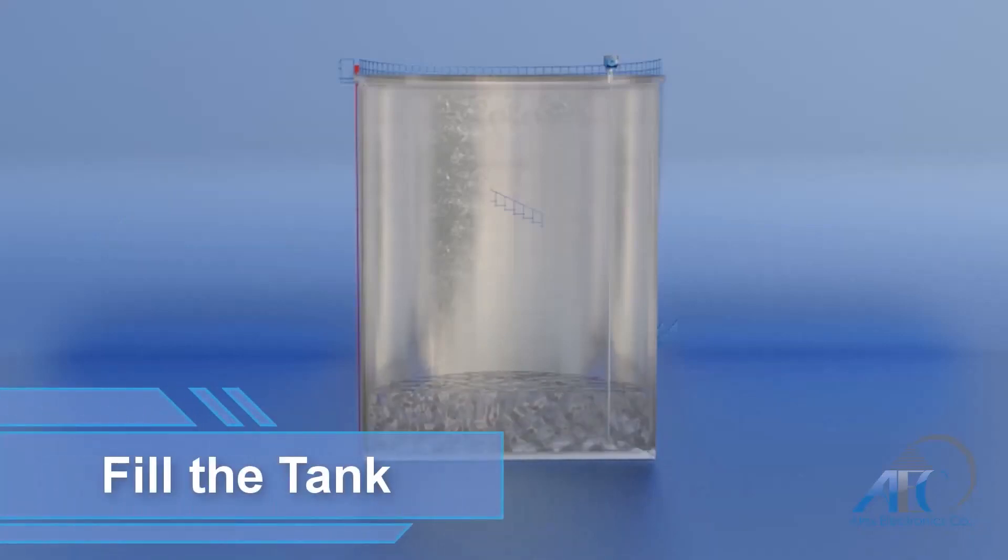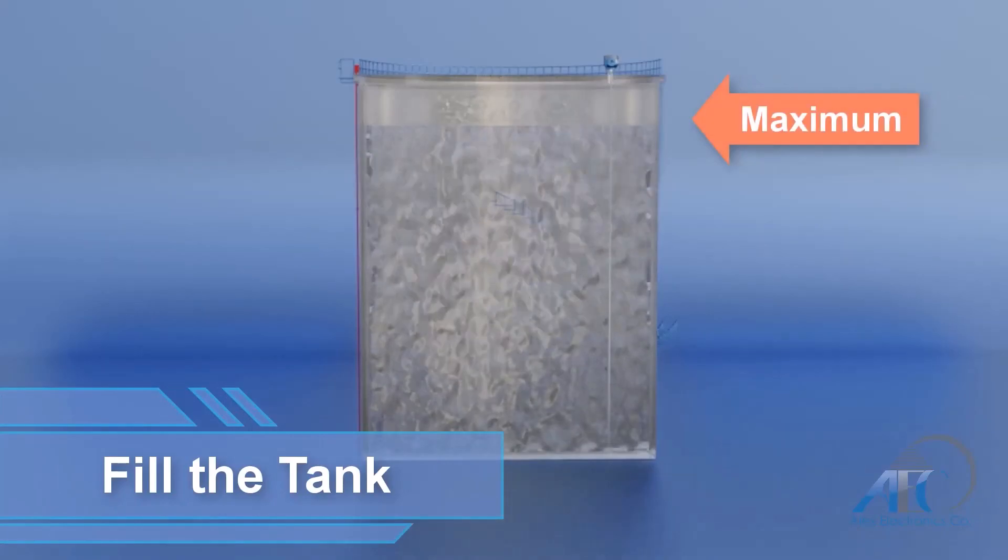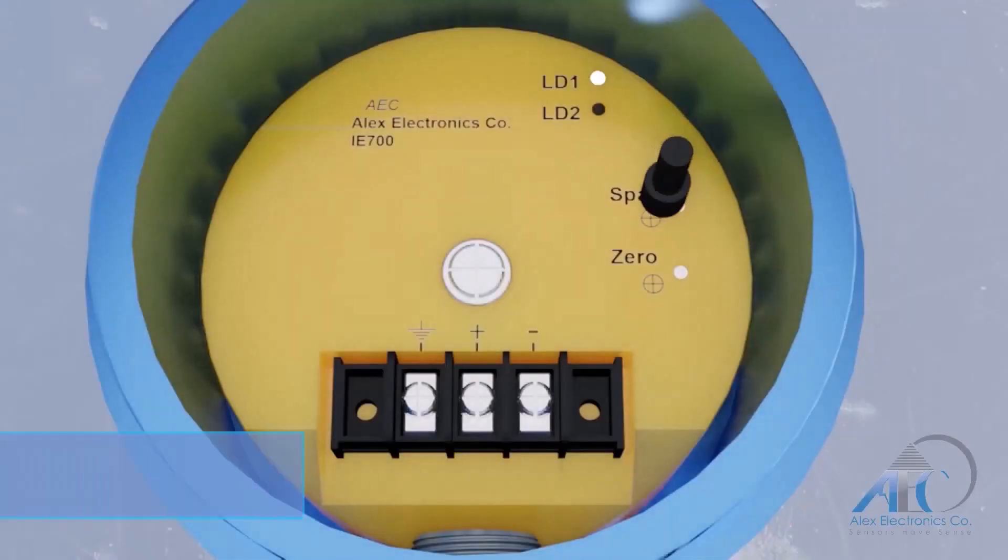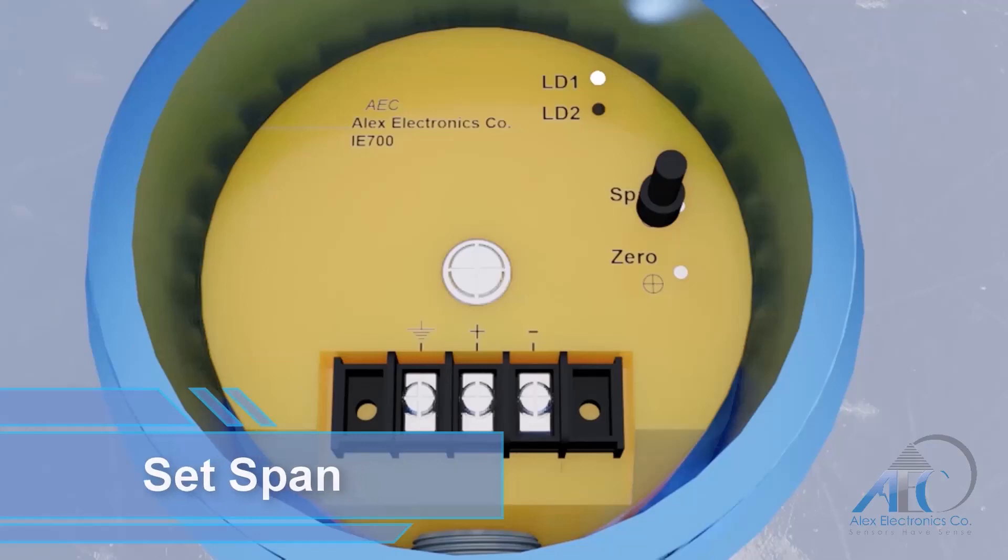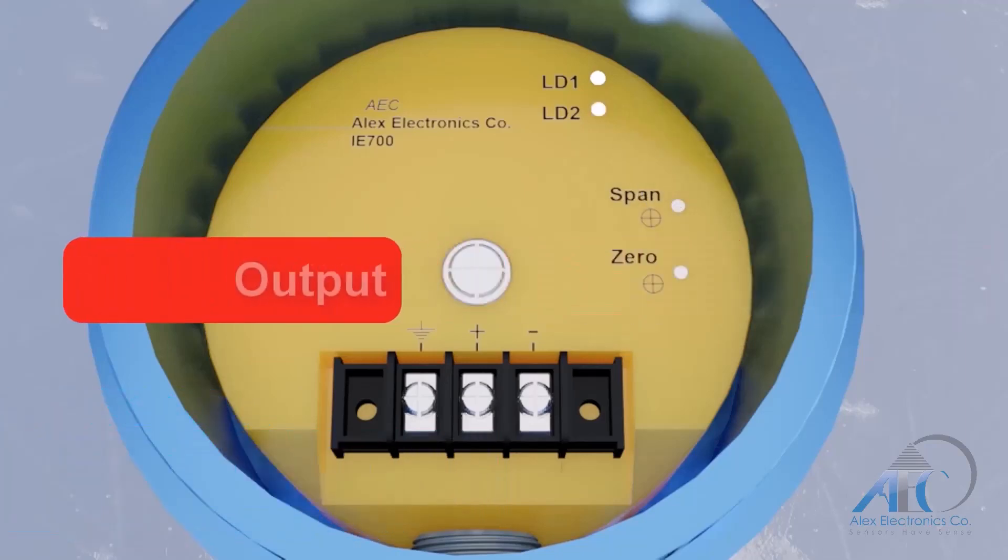To set the span, you need first to fill the tank to its maximum level. Then, use the magnetic pen with the span programming circle in the same way as shown previously. At this point the output signal is 20 mA.